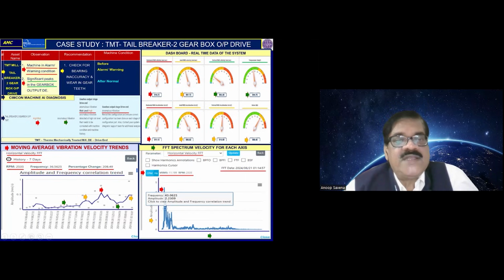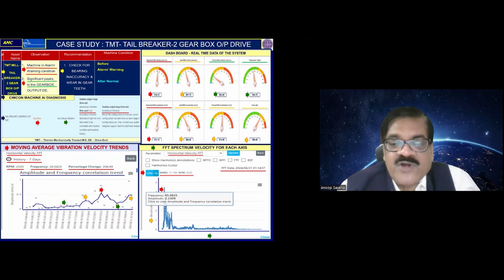So there were two reports - one from the system, which gave 3 or 4 options, and the other where human intelligence comes in. You have to choose which is best as per your machine's working and operating conditions, because AI will only give you short suggestions. These are the faults - maybe bearing is defective, gear is defective, or alignment is a problem - but you have to choose from your shop floor experience which is best suited.